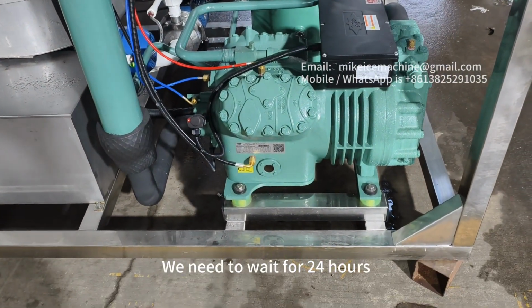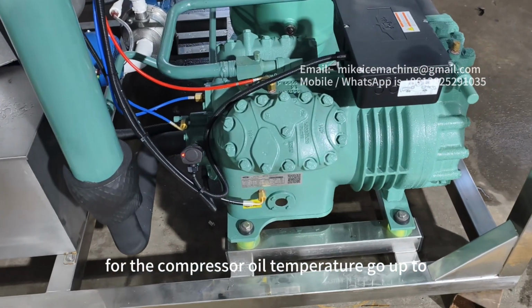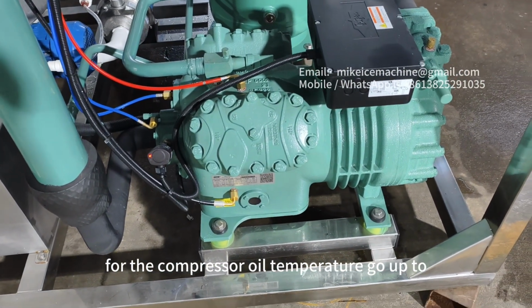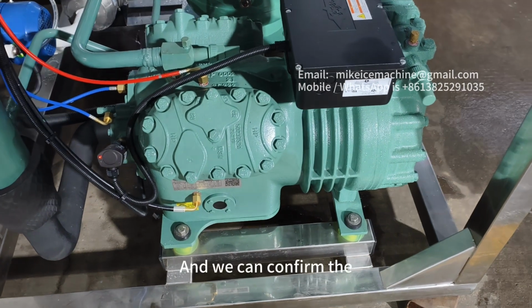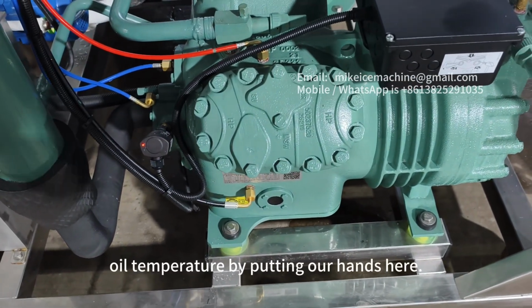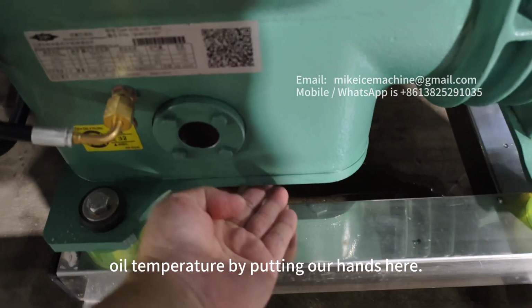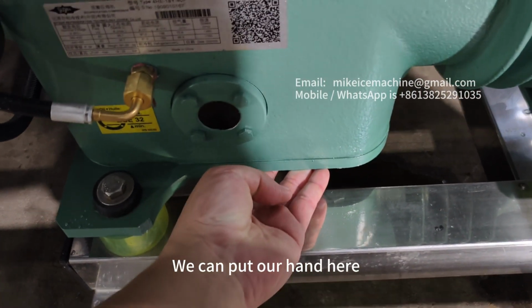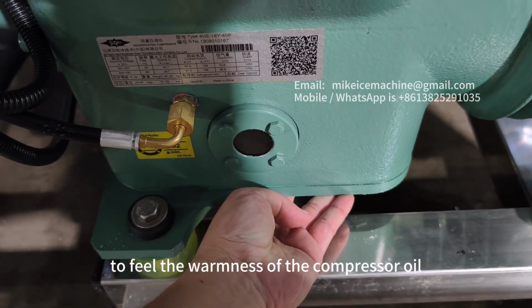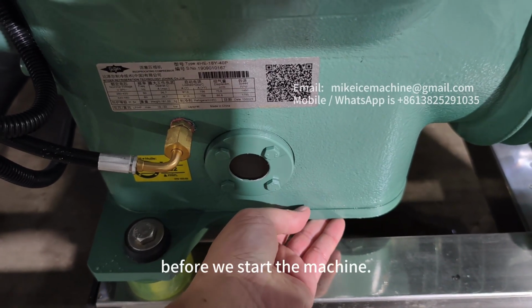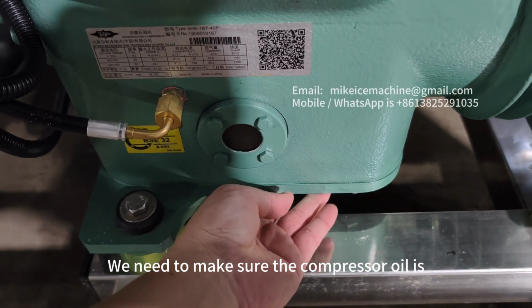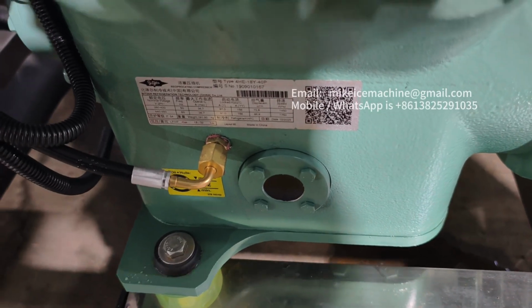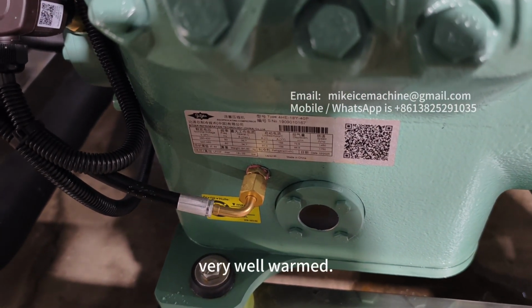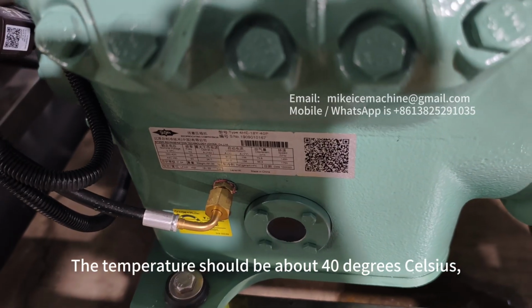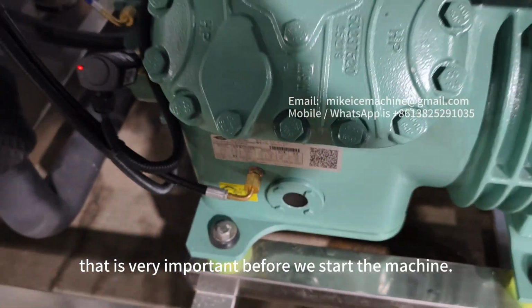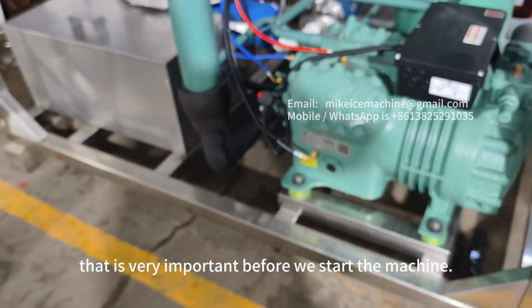We need to wait for 24 hours for the compressor oil temperature to go up to 42 degrees Celsius. And we can confirm the oil temperature by putting our hand here to feel the warmness of the compressor oil. Before we start the machine, we need to make sure the compressor oil is very well warmed. The temperature should be about 40 degrees Celsius. That is very important before we start the machine.